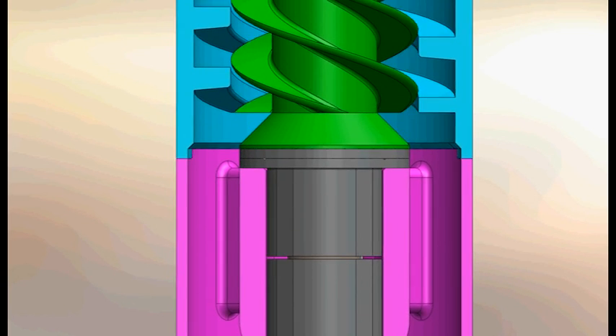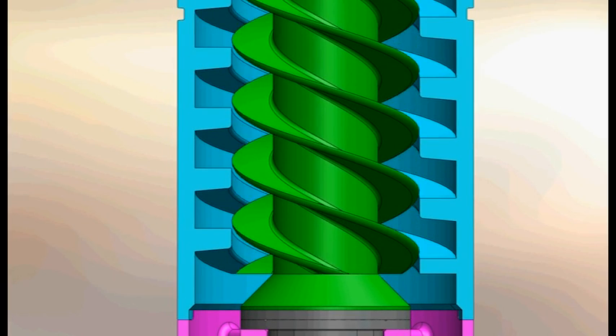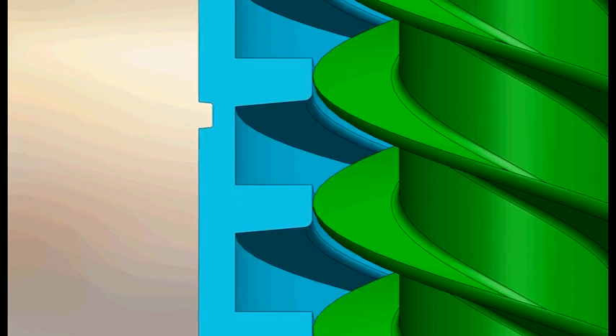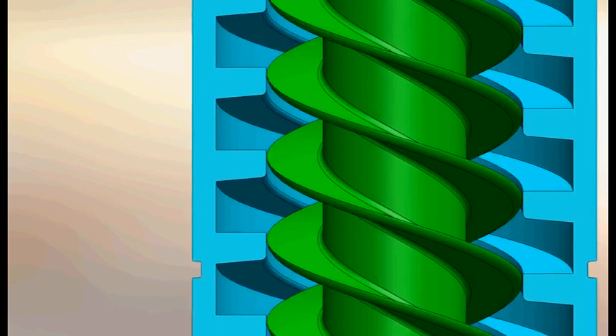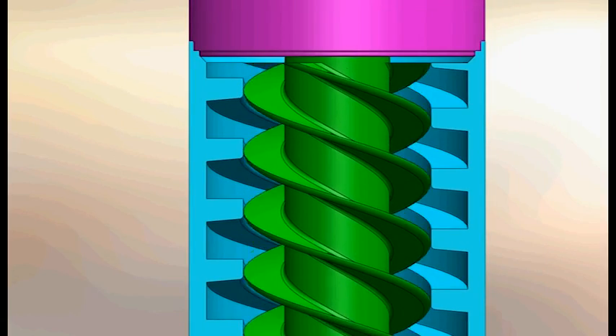The solution of liquids, solids, and gas enters the bottom of the rotor. The rotation of the rotor imparts spin to the solution moving the fluid upward. The upward lift of the liquid creates a liquid seal forming a boundary layer between the rotor vanes and stator channels.